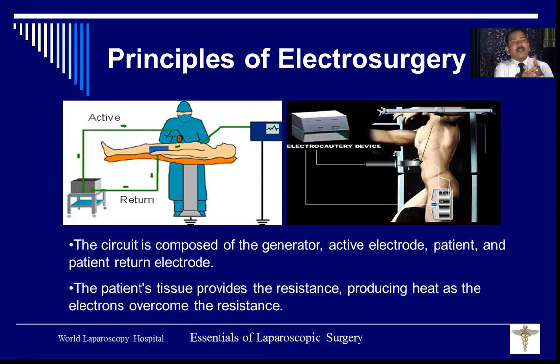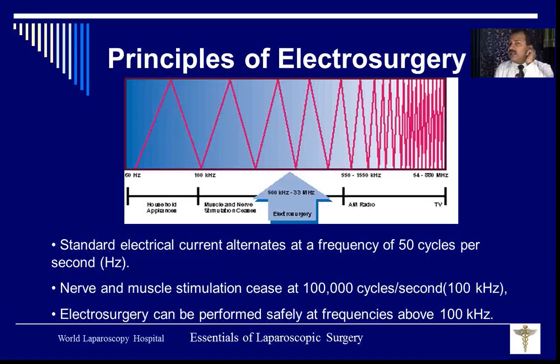Sometimes if the patient has not removed all the ornaments, like the patient is wearing a nose ring or ear ring or finger rings, and if it is touching some uninsulated part of the metal or saline stand or headrest metal part, then this metal will make contact with the metal of the surrounding equipment, and current will start traveling through these metal parts and the finger of the patient will burn. So all the ornaments have to be removed. If you cannot remove some of them, you can put some sponge and apply a bandage so that at least it should not touch any uninsulated part of the OT table or any of the other equipment.